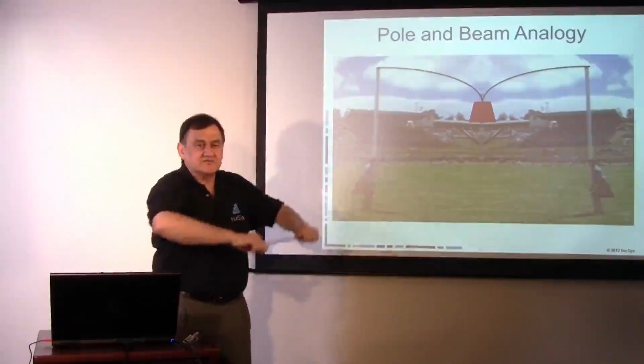So a strong bus is when we're close to what we call a dynamic megavar source, and the voltage doesn't change significantly as we add load. A strong bus is like having a very short distance—we can add load here, but our transmission line is very short, has low reactance, and we don't get a lot of sag as we add a different force. A weak bus is when we have a very long line with very high reactance, and we get a lot of sag as we come on down.